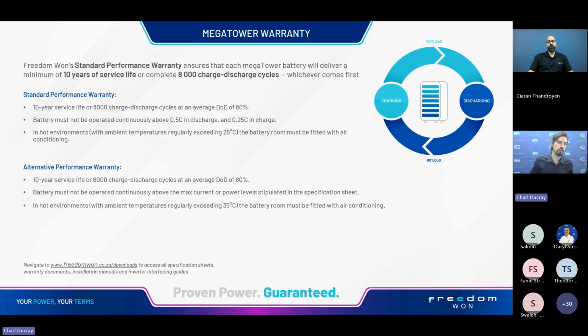So in this scenario, we still offer a 10-year service life, but we support 6,000 charge/discharge cycles at an average DoD of 80%. Going back to the C rating point, we prefer to look at what the site requires, what your loads require, what currents you need at max, and we size the batteries accordingly. We don't look at the C rating as a limitation of the battery, but size the capacity according to what your site requires.